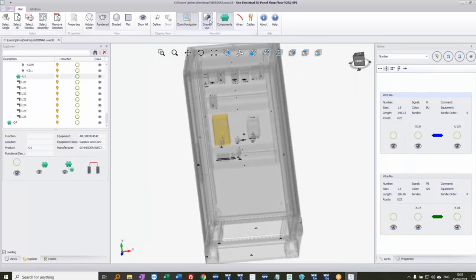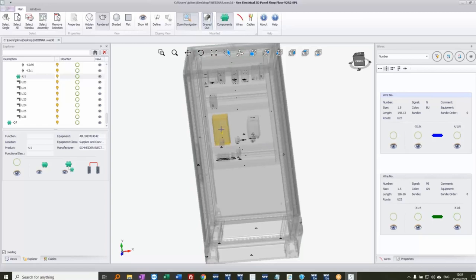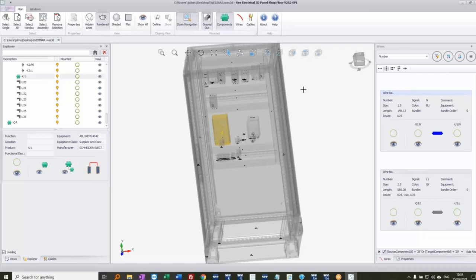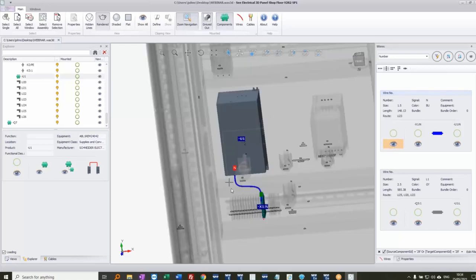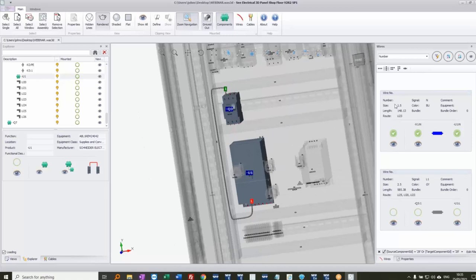I can turn off the ghosting from the top toolbar. The reason for the ghosted format is that clicking a component shows a list of wires connected to it — for instance everything connected to the power supply. In the separate Wires panel I can select the first wire, and not only does it highlight in the 3D view, it also shows which connection point it connects to, the wire size, color, signal name, length, and the route it takes.